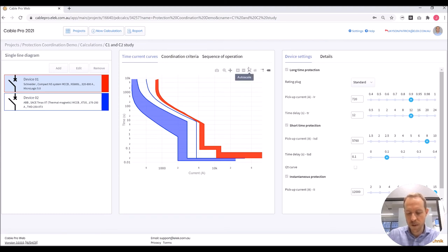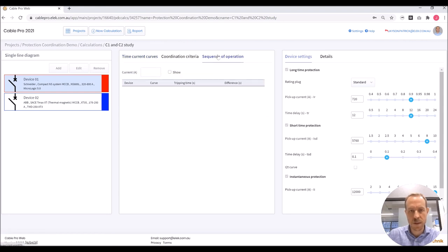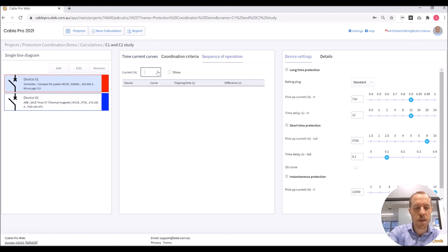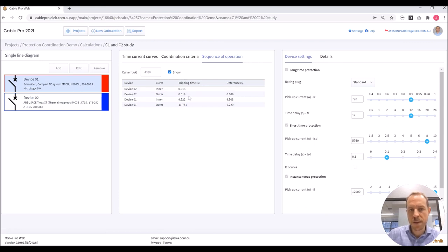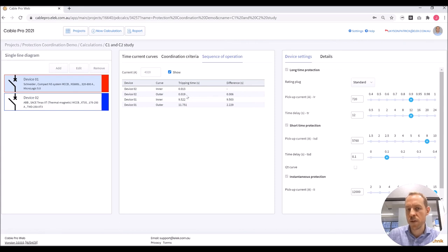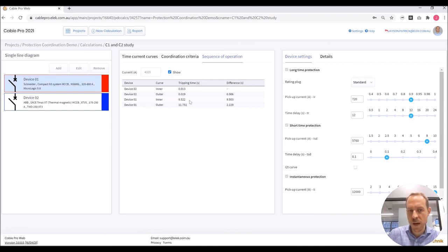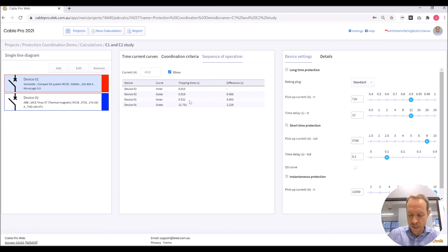We can also look at the tripping sequence of operation for the arcing fault level of 4320 amps. So I will enter that value here. You can see that the tripping time for that arcing fault current for device 2, which is the downstream breaker C2, is under 0.02 seconds. And the tripping time for device 1, which is C1, is around 9.5 seconds. So you can clearly tell that these breakers are discriminated.